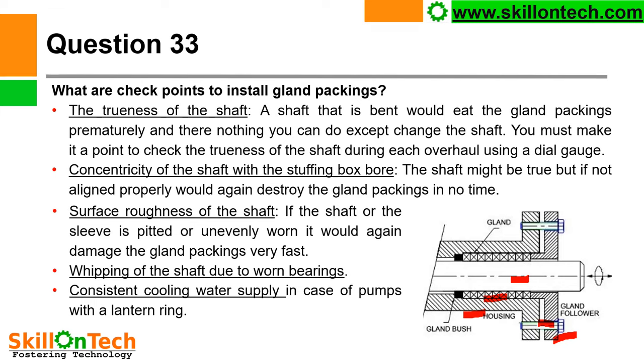Concentricity of the shaft with the stuffing box bore. The shaft might be true but if not aligned properly, would again destroy the gland packing in no time. So the axis of the shaft and axis of the stuffing box housing shall be concentric. Surface roughness of the shaft: if the shaft or the sleeve is pitted or unevenly worn, it would again damage the gland packing very fast. Generally there may be a shaft sleeve over the shaft, and gland packings are provided over the shaft sleeve. If your shaft sleeve is pitted, then it will also damage the gland packings very fast, so the shaft sleeve should be smooth and perfect.